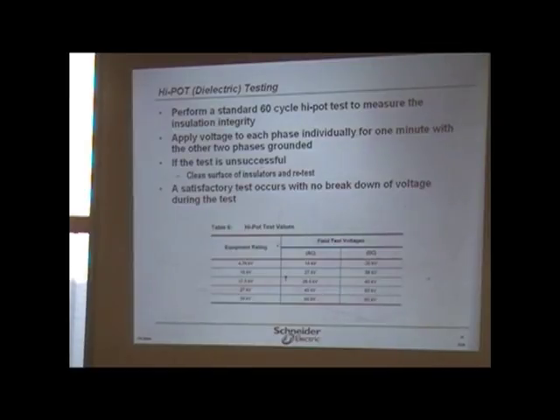If it holds it 2.5 times, then you know that the integrity of that bottle or that gas is inert, it's good, and everything else. You haven't lost your pressure in there. And that's what you're trying to make sure, that it's pressurized more than anything else. On the HVO switches and stuff like that, they're basically the same thing.